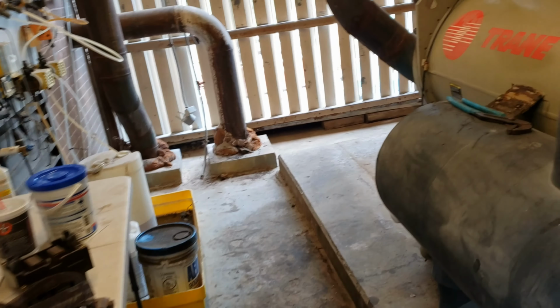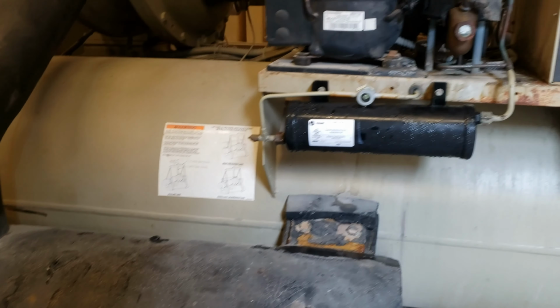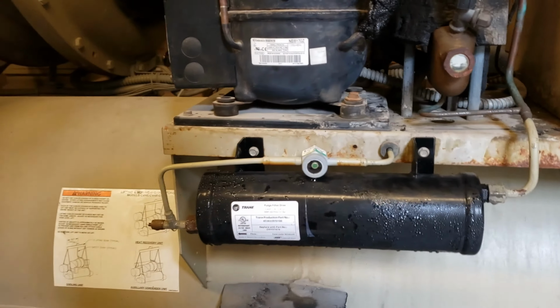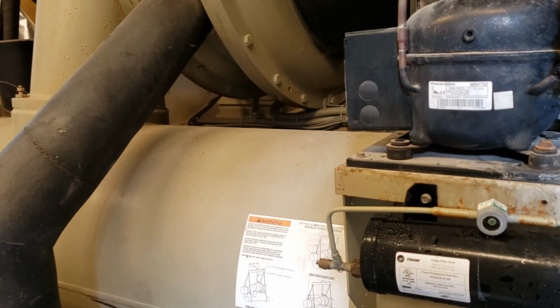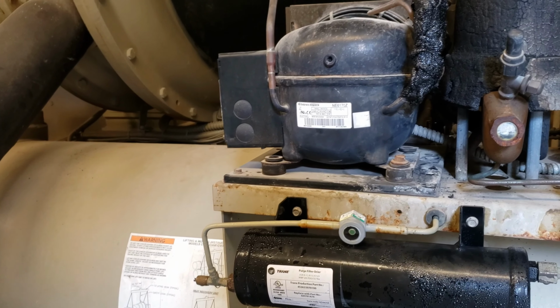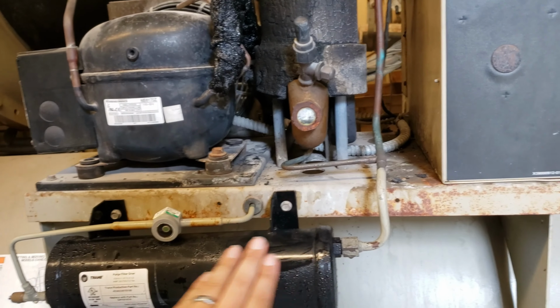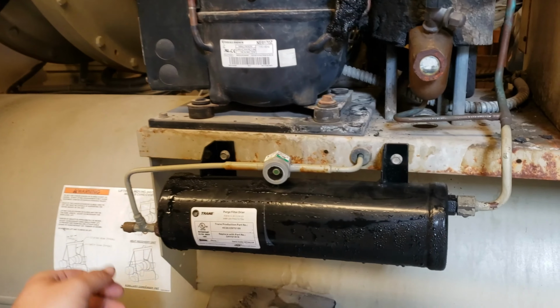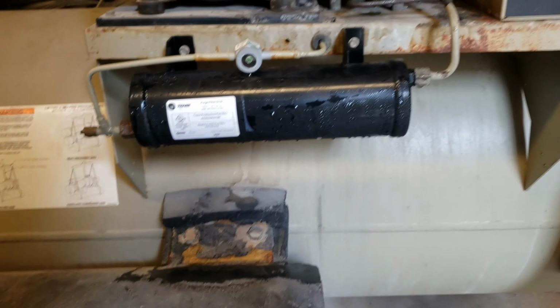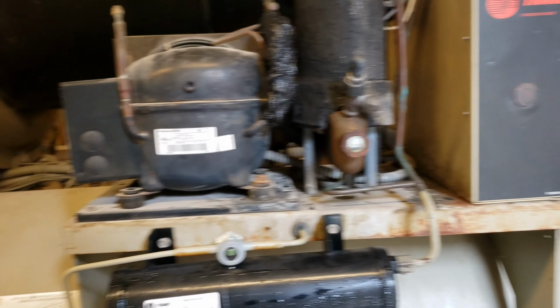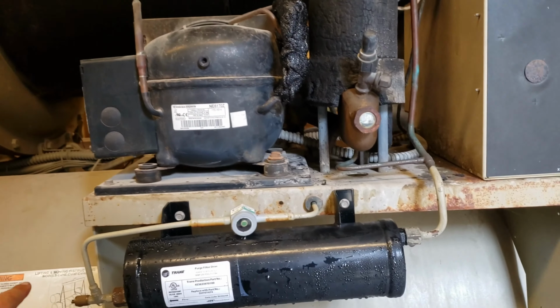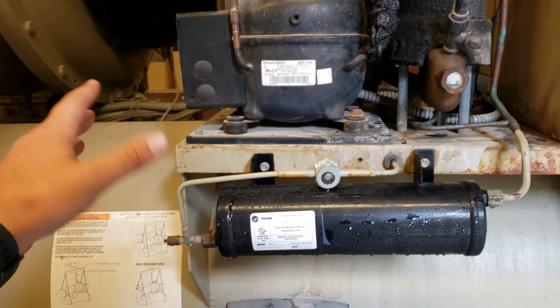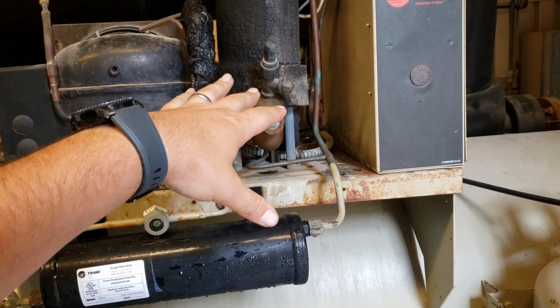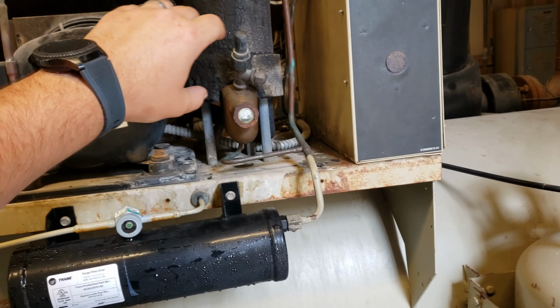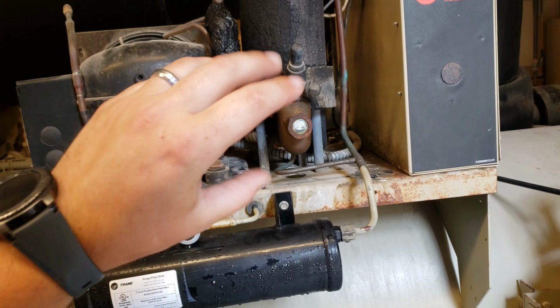And so it takes that temperature and then converts that temperature into a pressure instead of vice versa. So that's just something you see on this Trane, the CVHEs, CVHFs specifically. I know they do it on other models as well. So anyway, it takes that saturation temp, and then it uses that in comparison to the suction temp, and it wants those temperatures to be so far apart.